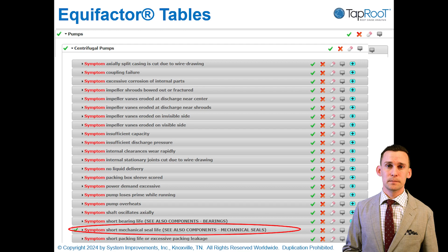So we'll take a quick look at the troubleshooting tables and what those look like. Here we have, under pumps, centrifugal pumps, all the possible things that can go wrong. But in a situation where I had a failure, I only care about the symptom I'm seeing, so I get rid of everything else except the green check mark under short mechanical seal life, because that's the problem I'm seeing.